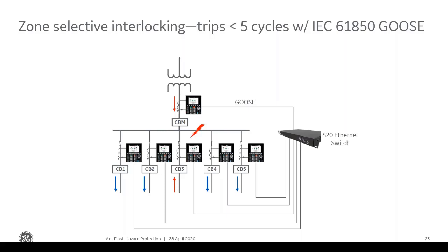This particular one I'm talking about uses IEC 61850 GOOSE messages, which is a way to communicate peer-to-peer from relay to relay. So if there's a downstream fault, the relay on that feeder, for example feeder 3, senses the downstream fault and sends a blocking signal back to the main relay, telling it, hey, the fault's in my zone, it's not on the bus, you don't need to trip. If the main relay does not receive a blocking signal from any of the downstream devices, then it knows the fault's on the bus, and it's going to trip.